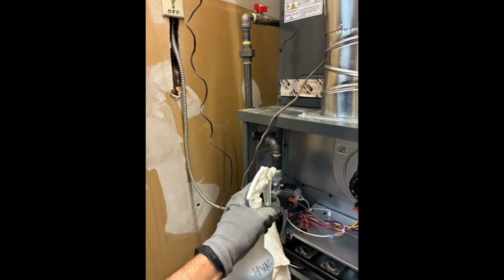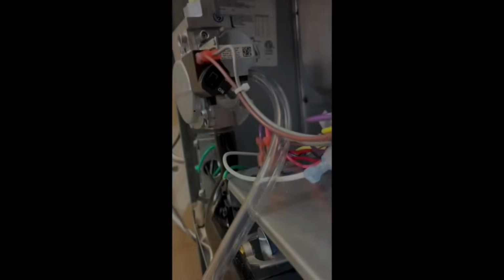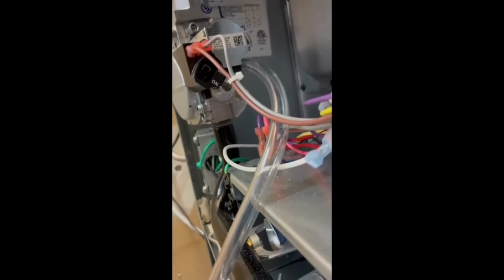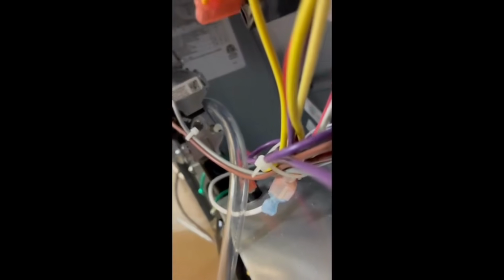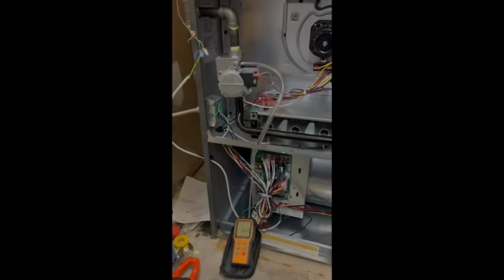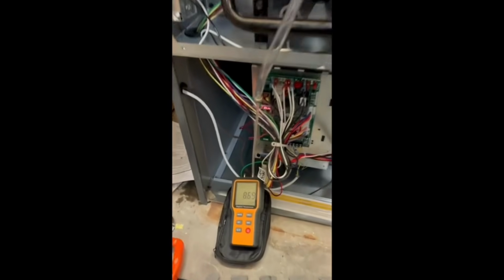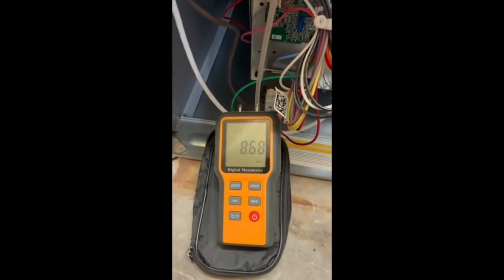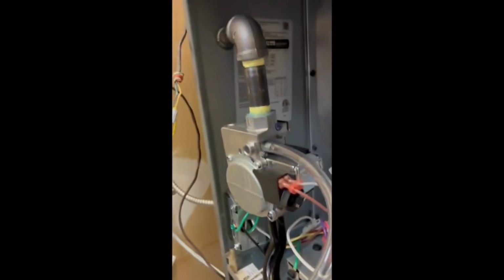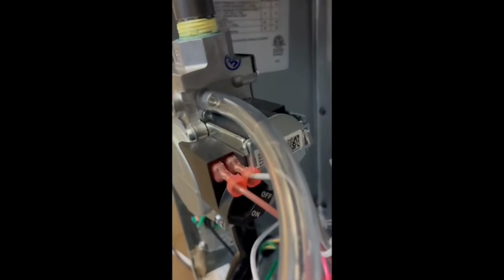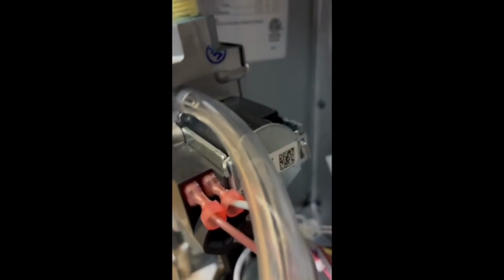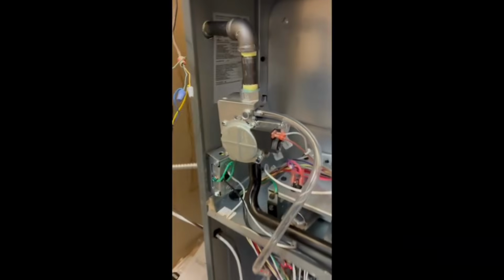We're going to check the furnace. So I turn on the gas. I'm checking for leaks at all my joints with bubble leak detector. Next, my inlet gas pressure and outlet gas pressure on the gas valve. The manufacturer gives you a range. We're at 8.6 inches of water column on the inlet of the gas valve. 10 is a max, so we're within tolerance. And on this kind, you don't take that Allen all the way out. You just unscrew it a couple turns, so just FYI.